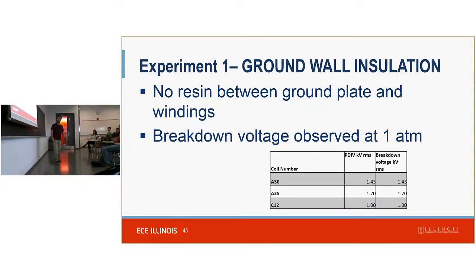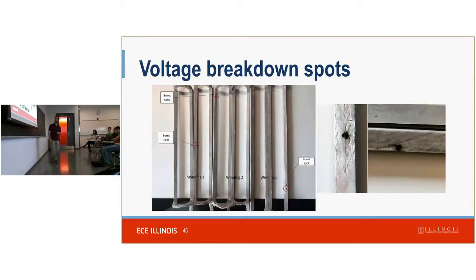When initially doing the test, we found breakdown voltage below the level that we really were targeting, at about 1 to 1.7 kV RMS. That was concerningly small, and this was full breakdown, not just partial discharge. So basically it destroyed the coils. And here you can see the spots where the breakdown occurred. You can see the burnt spots. It's going to be hard to see on these ones because they're small, but here's a closer-up picture.